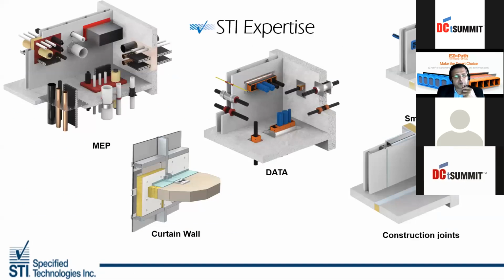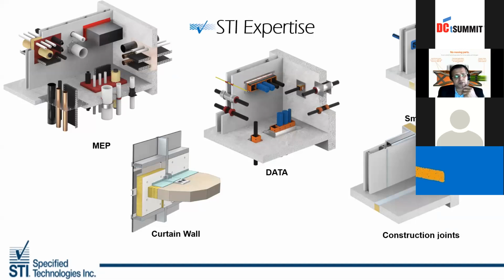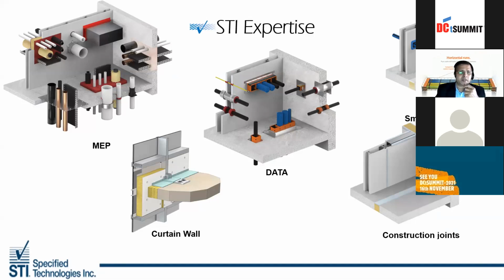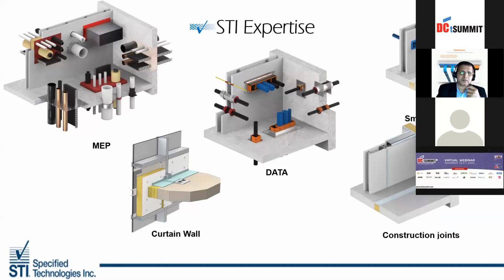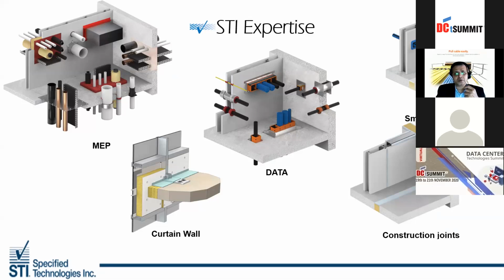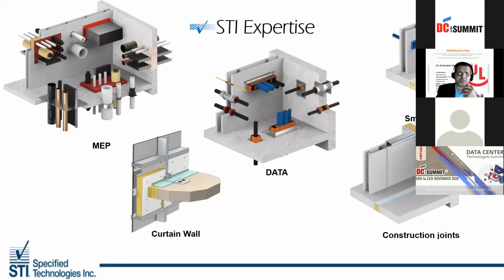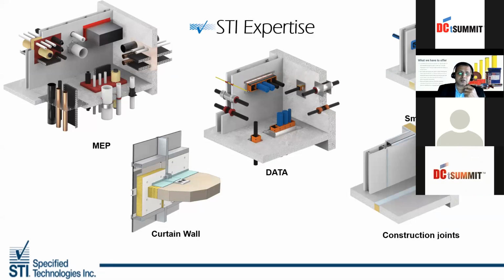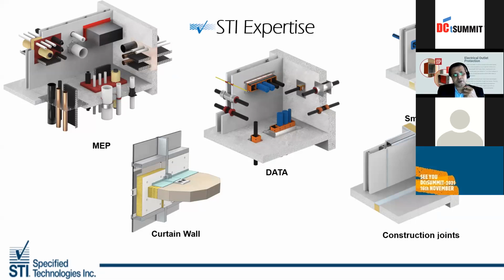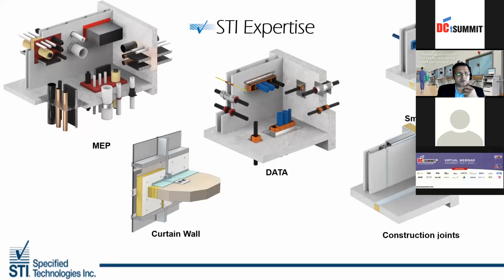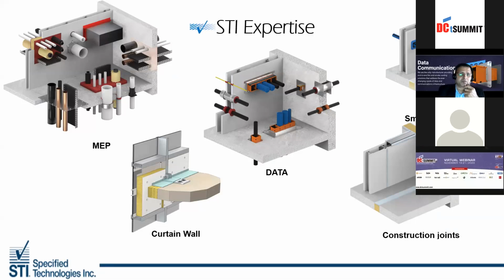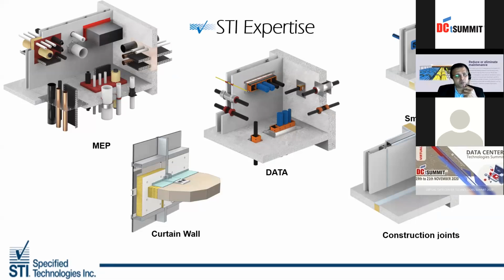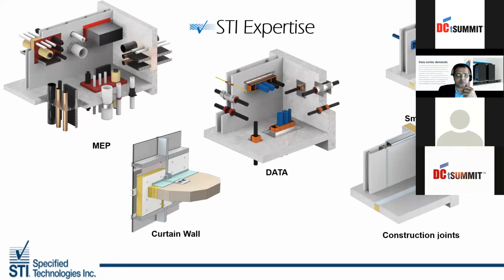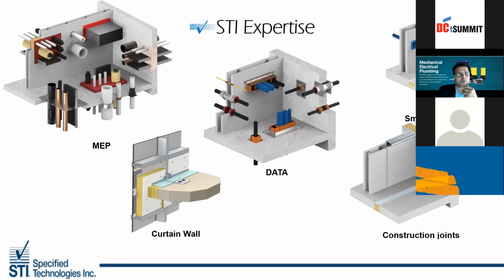In a project, where all STI can support you is the MEP. It can be the mechanical, electrical, and plumbing services. You have the data centers, the smoke and acoustical, where only a cold smoke is required. Yes, we have products to support those areas also. The construction joints and the curtain wall. Curtain wall will be an important one because in any given commercial or residential building where there's a curtain wall, the gap between the perimeter and the facade is the most important area where the smoke and the fire travel to the upper floors. So we have almost 130 UL tested systems, as per the design of the consultants, to support the project.